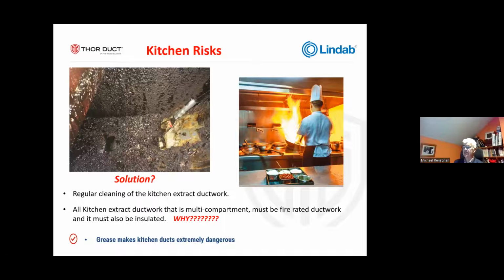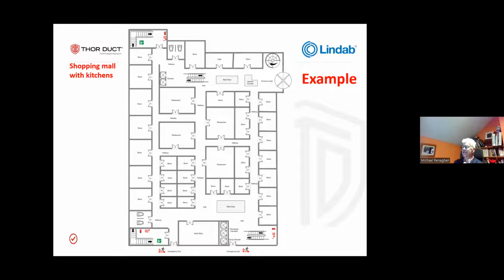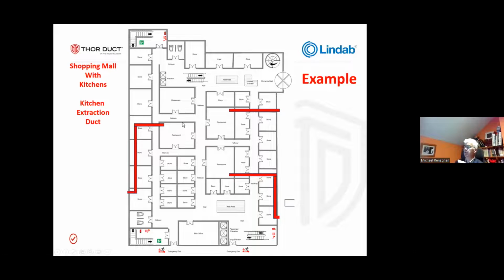So what is the risk? How does this present itself? So we have a shopping center, restaurants in the middle because we like to have a bit of footfall moving past shops. You have a kitchen extract traveling from the restaurant to the outside. Many times it'll cross stores like they do in all of these scenarios. If fire starts, and note this, not a fire inside the restaurant, because inside the kitchen area, all of that's under control. We have suppression systems there. So it's not really that big an issue, but it's a fire somewhere else.